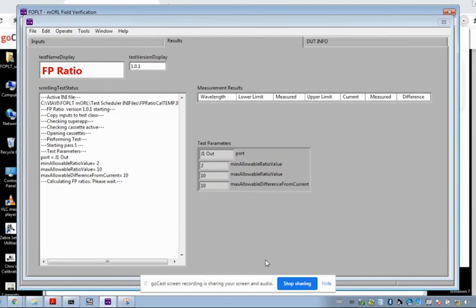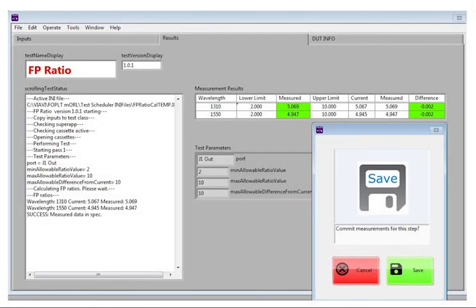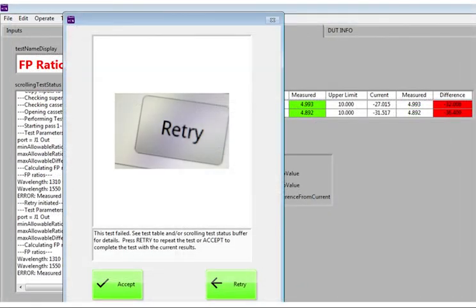The system is now measuring and setting the front panel power ratio to make sure it's within the specified range. It takes a while, because it isn't possible to calibrate a module that has been set up and operating with an integrating sphere. A module set up to operate with one will fail this part of the process because the integrating sphere operating power level is considerably different than expected. You can see that here in the difference values shown in red.